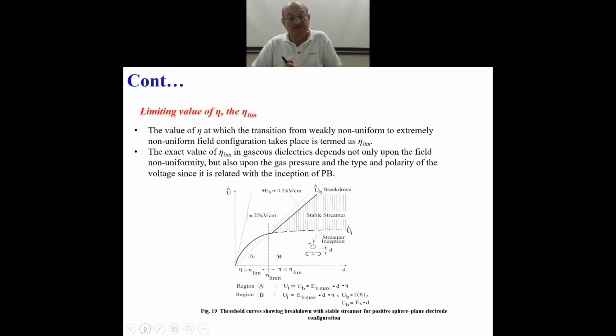Extremely non-uniform field means the breakdown will be preceded by partial breakdown activity. That means when you maintain a certain voltage, there will be continuous corona activity, partial breakdown activity, in the field. Whereas in a weakly non-uniform field, as I mentioned, there is no continuous partial breakdown activity. As soon as the partial breakdown begins, the total or complete or global breakdown is achieved.